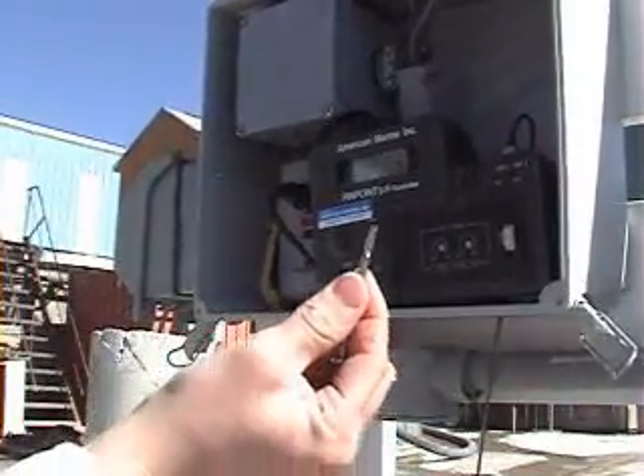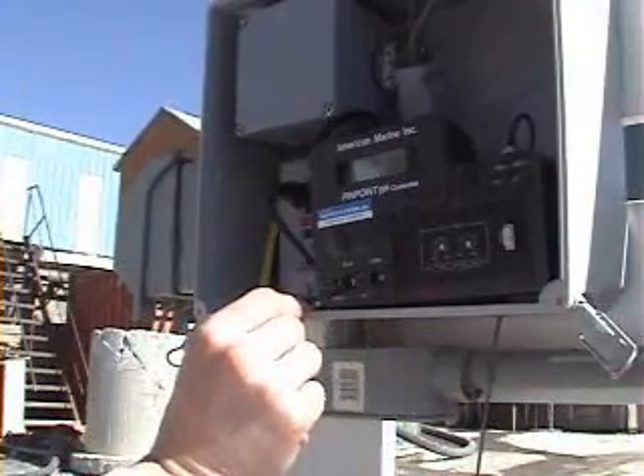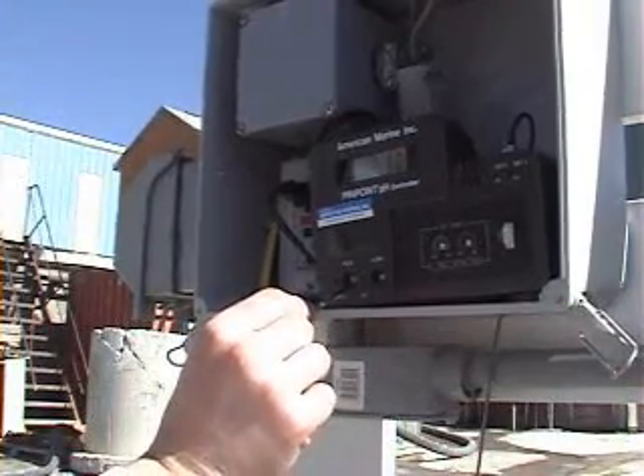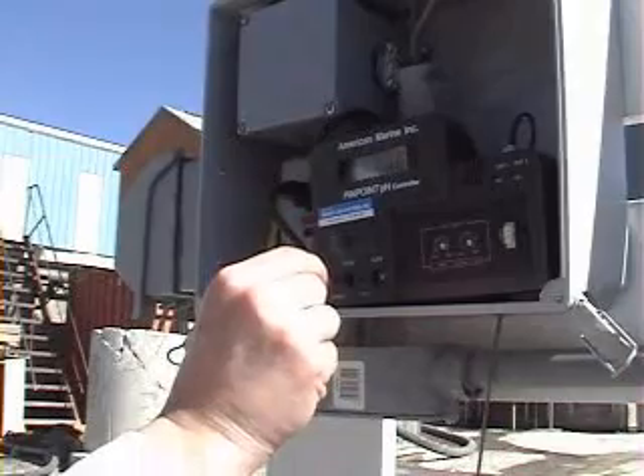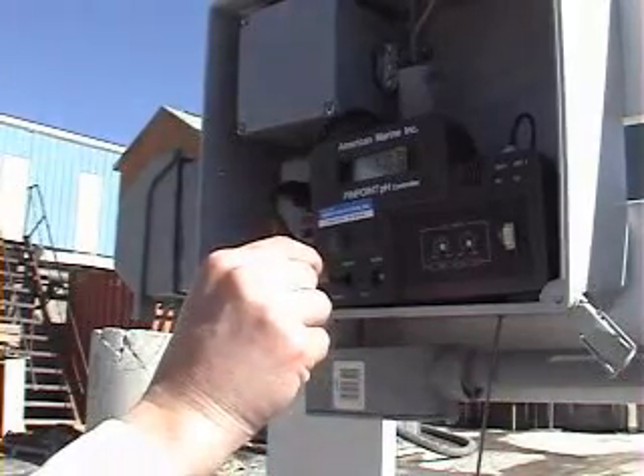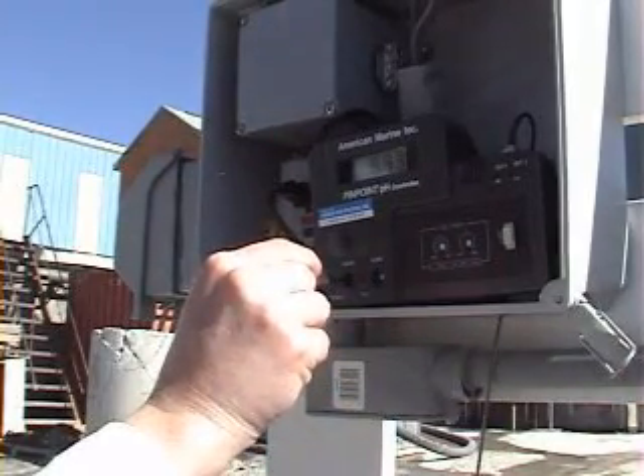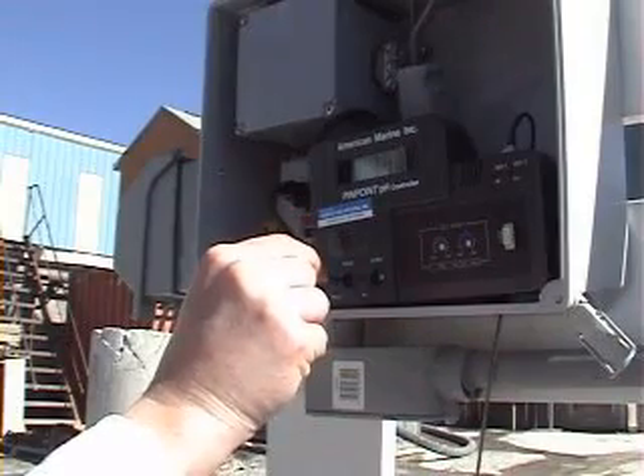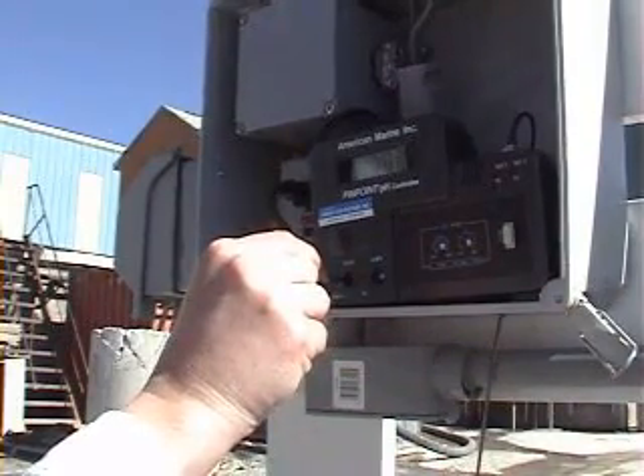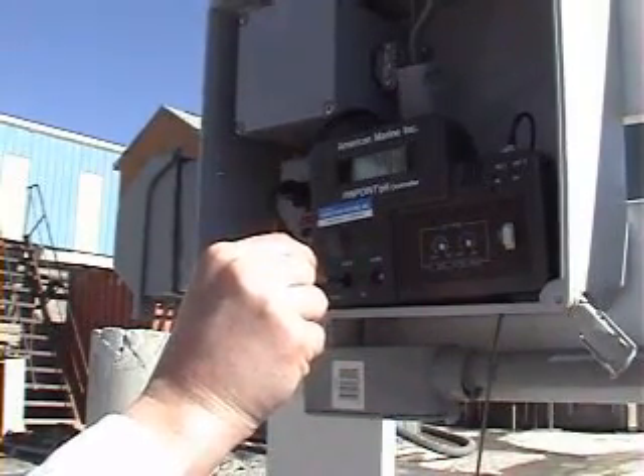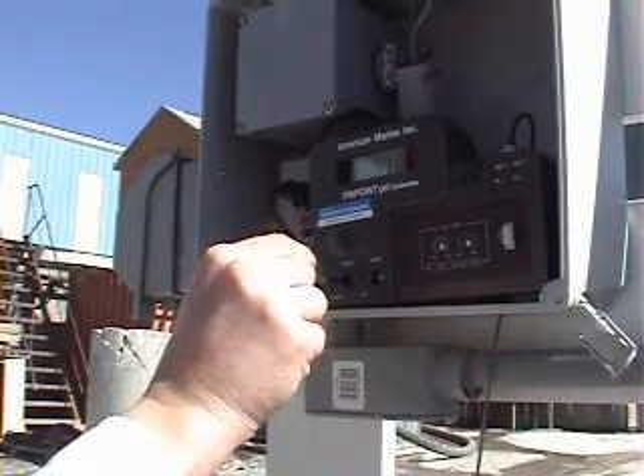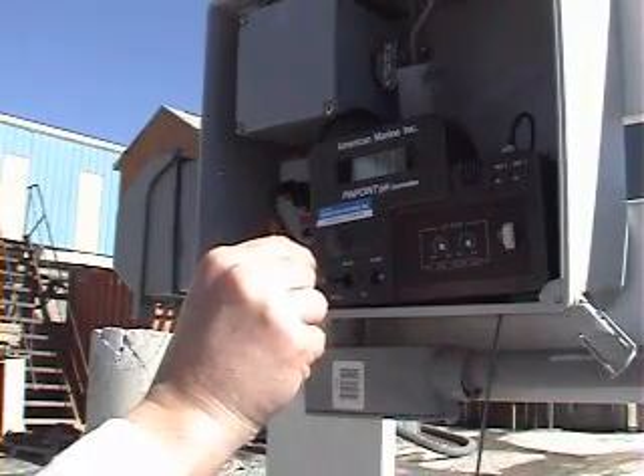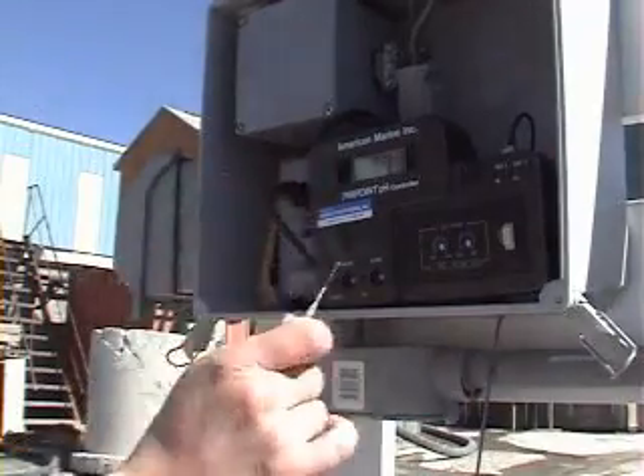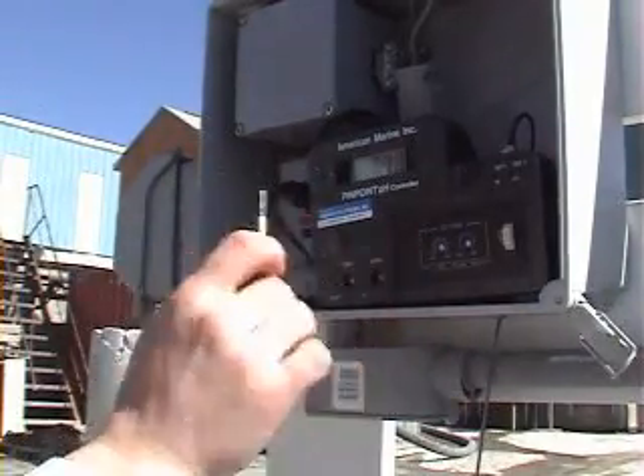So now what I'm going to do is take my flathead screwdriver. On the left side here, the calib side of the calibration dials, I'm going to insert the screwdriver and simply turn it back just a tad until I get around 7. Now, sometimes you might be 100th or so off. If I have 7.01 or 6.99, that's fine. Close to 7 is fine. So we're there. It looks like it's going to jump back and forth between 7 and 7.01.